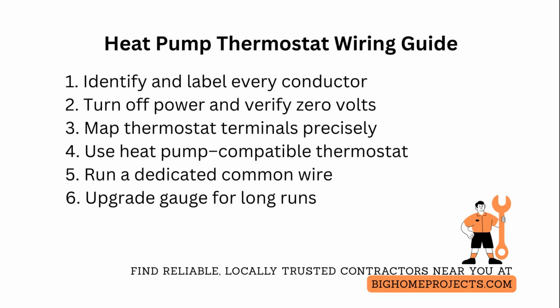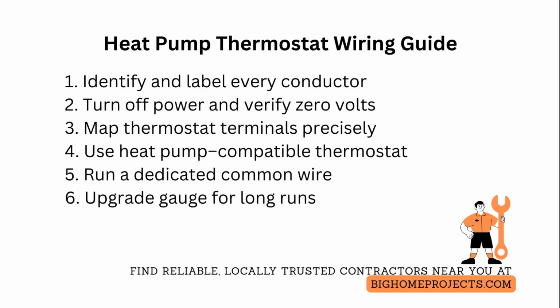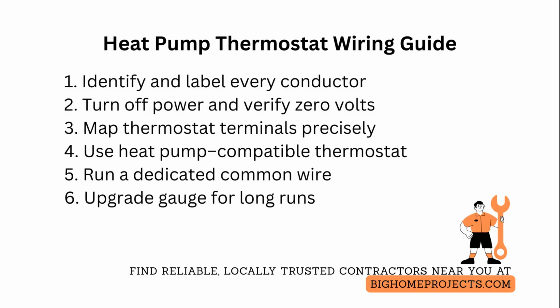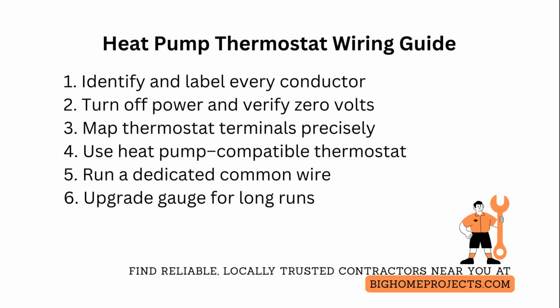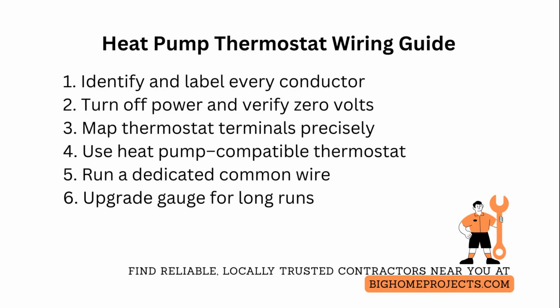Use a thermostat that explicitly supports heat pump systems and configure it for single-stage or multi-stage heat pump operation, selecting correct changeover orientation so the thermostat energizes the reversing valve for heating or cooling correctly. If your system uses a common wire or the thermostat requires one for power, run a dedicated common from the control board rather than trying to steal power from the fan or other circuits.